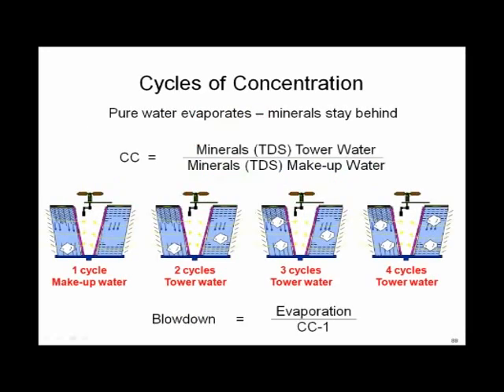Now, we kind of went through the discharge piping pretty quickly there, but that was the point, and you've got to follow the codes, and you want to make sure you don't drain them down. We're going to show an example of a problem in a few minutes. Let's look quickly at cycles of concentration, because it's in the code for the first time. And a lot of engineers and people have never really dealt with this. They've heard about cycles of concentration in a cooling tower. In other words, as I evaporate this water off in a tower, what I call the rocks stay behind. So sooner or later, I've got to have some blowdown water going down the drain, or my tower's going to cake up as one great big rock. And this is determined by the cycles of concentration.